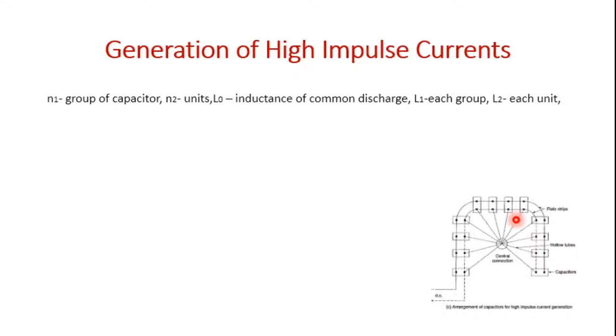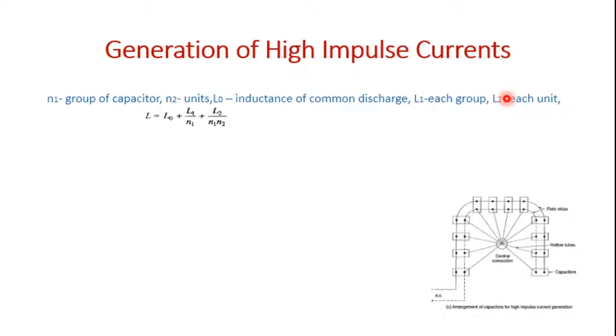If there are N1 number of groups of capacitors, each consisting of N2 units, then L0 is the inductance of the common discharge path, L1 is that of each group, and L2 is that of each unit. The effective inductance L is given as: L = L0 + L1/N1 + L2/(N1 × N2).